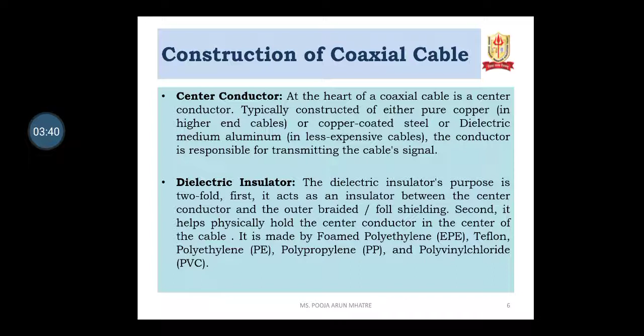Third is the braided shield. Interference tends to come in two different flavors: electromagnetic interference, that is EMI, and radio frequency interference, that is RFI. The EMI interference is often caused by heavy power lines, cell phone signals, etc. A braided shield protects the signals from EMI, and often ranges anywhere from 30% to 95% coverage. The higher the coverage, the better the protection.